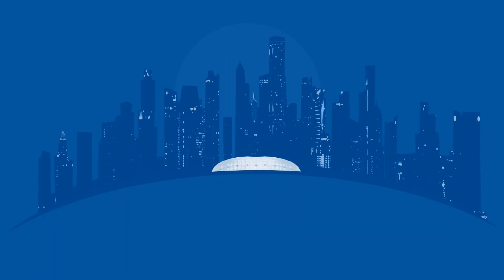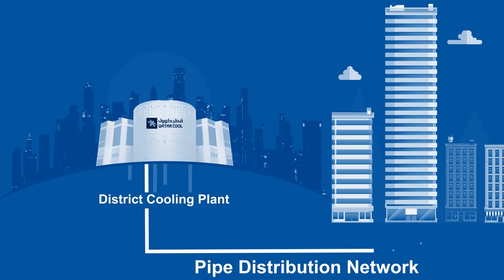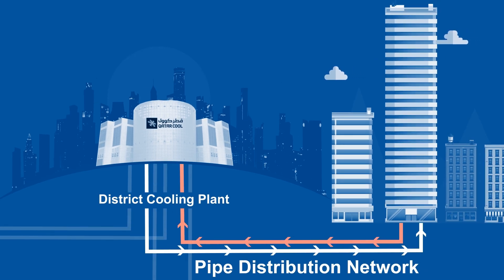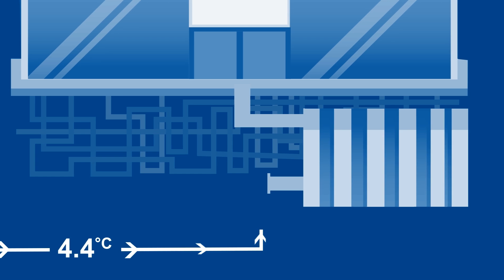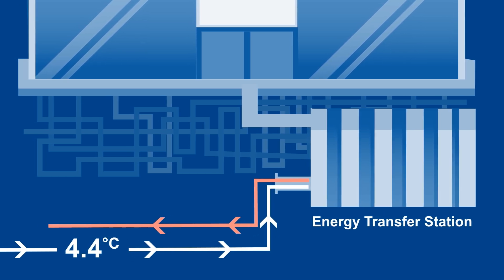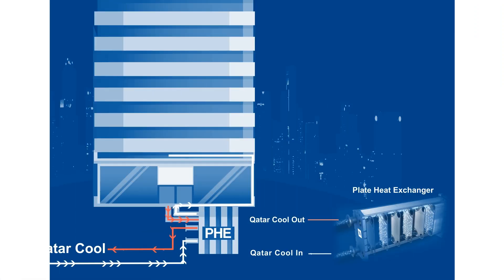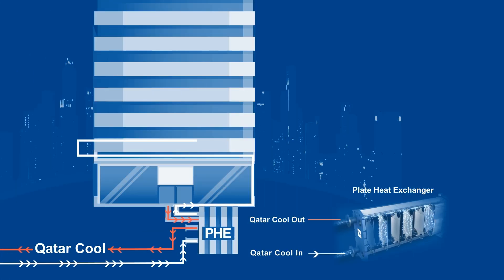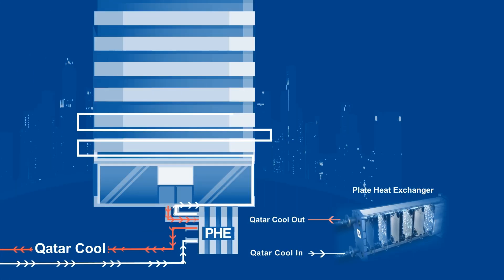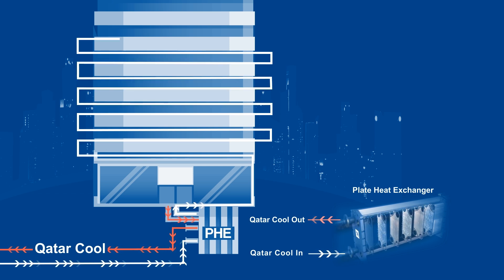It starts at a district cooling plant where the water is chilled and distributed through the pipe distribution network. The chilled water is pumped from the plant through the pipe distribution network at a temperature of 4.4 degrees Celsius. When the water reaches the energy transfer station in the basement, the chilled water is used to cool down the building's water through the plate heat exchanger.